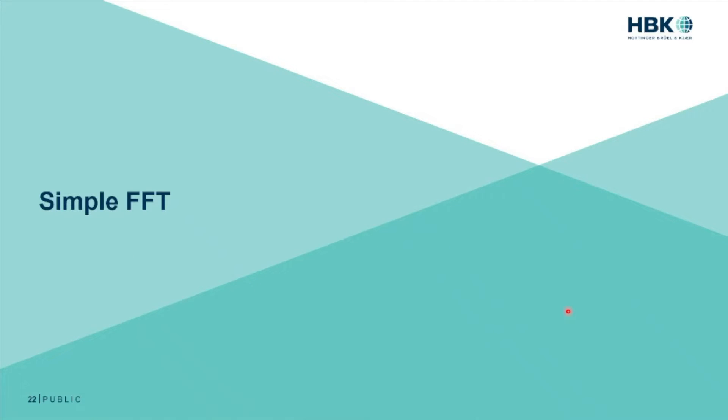But in our software, we can do things like a simple FFT. I showed an example of this earlier, but it is a really powerful tool. We do show this live in the software. If you're measuring a voltage and a current, you can look at what is my fundamental? What are my harmonics in 5th, 7th, 11th, 13th? And then what are my switching effects? And we can really see the full spectrum out to the bandwidth of the amplifier. So we can get a good understanding and kind of a gut feel on what's happening in the frequency domain.